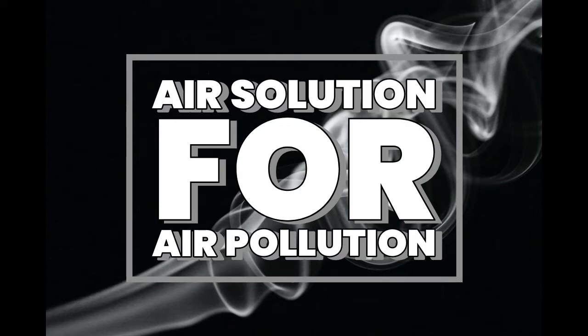What were the considerations you assessed when deciding on the design of the wet scrubber? The first characteristic we thought of was the orientation of the scrubber because a wet scrubber can either be vertical or horizontal. We decided on the wet scrubber being vertical since it is typically recommended if the rate of liquid accumulation is small. We assumed a small liquid accumulation because the discharge flow rates of the gases are not that problematically high. Vertical scrubbers also have higher removal efficiency than the horizontal ones.